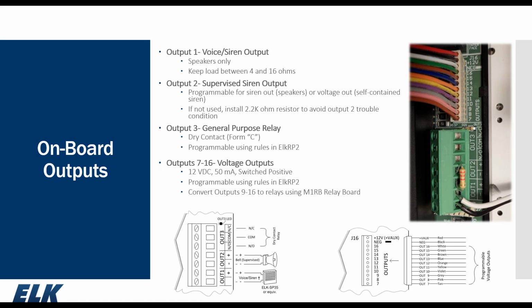Output 2 is a supervised siren output, typically for exterior devices, your exterior speaker, or you can convert output 2 into a voltage output, which would be 12 volt at 1 amp, so it's capable of driving a self-contained siren as long as it doesn't exceed the 1 amp rating. If you're not using output 2, if you're not going to have anything connected to that terminal, you need to make sure to put a 2.2k ohm resistor across output 2 positive and negative to prevent the output 2 trouble condition, just like we have in our picture here. With nothing connected, we want the resistor there to satisfy the supervision to prevent the output 2 trouble.